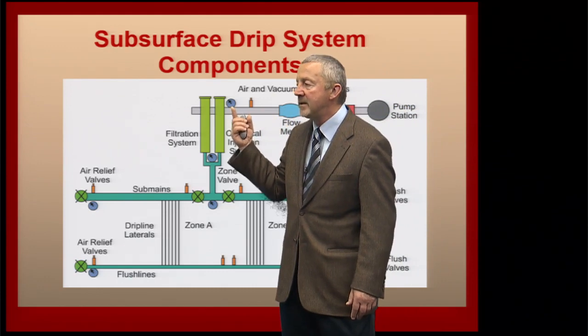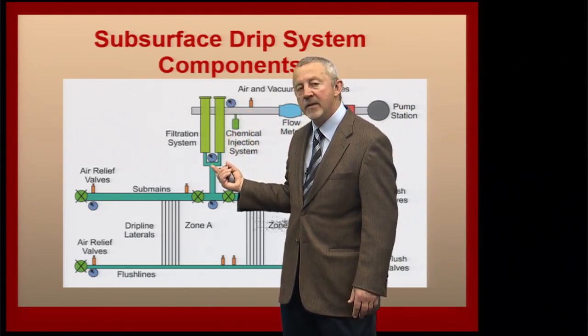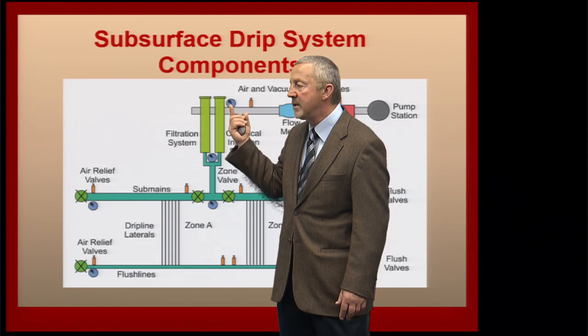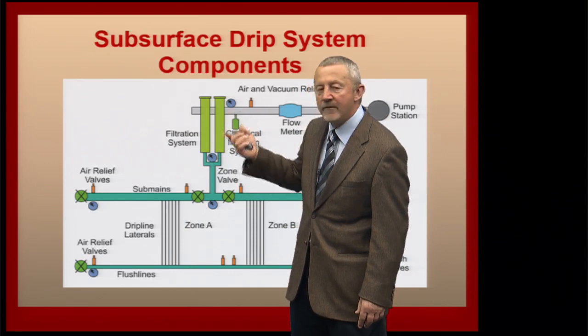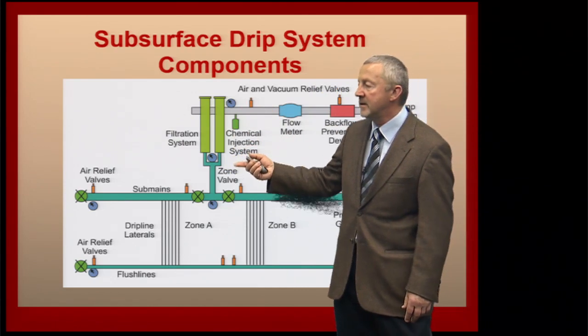It's also important that we have a pressure gauge located both upstream and downstream of our filtration system. When the difference in pressure between the inlet and the outlet gets increased so much, then we know we have to flush our filtration system out or replace the filter altogether, depending on the system.